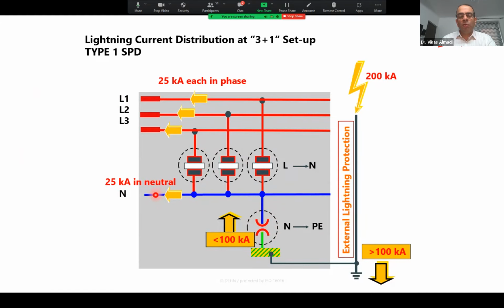So the division is in 4 lines, but out of these 4 lines, the arrestor above is in 3 lines. So every arrestor will carry 100 divided by 4, 25 kiloampere current, and the rest, 25 kiloampere current, will go direct. Whereas this arrestor, which is connected between neutral to earth, will carry 100 kiloampere current. So that is the division of the current. If you could connect it between line to earth, then all the arrestors will be connected to the same connection point, and you have 100 divided by 4, 25 kiloampere each, if you use a 4+0 system. But you are not using a 4+0 system, for the reasons you now know. So in the 3+1 system, 100 kiloampere and 25 kiloampere each.